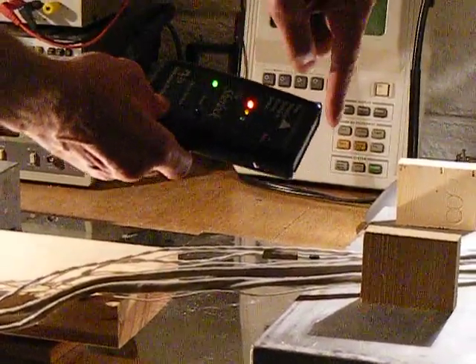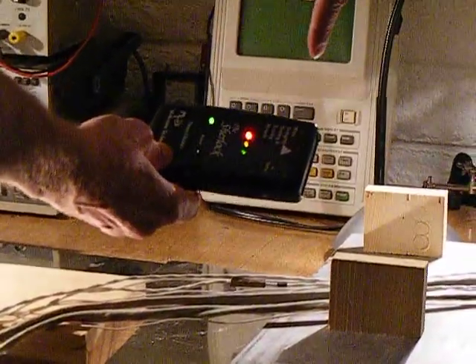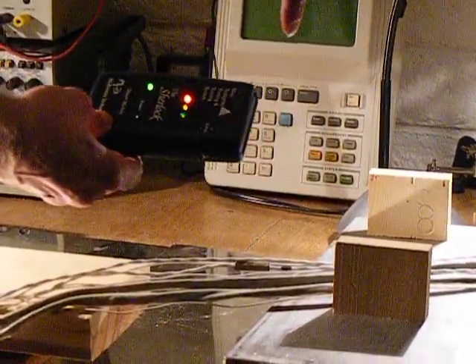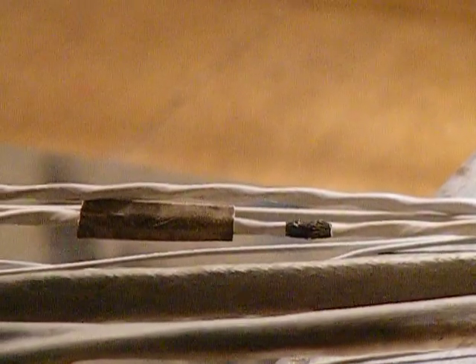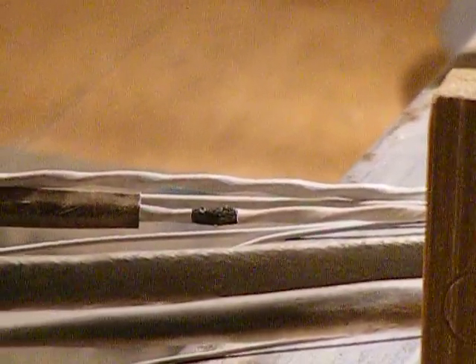And if we were to take this arrow, right where it starts to diminish, right there, follow that arrow straight down, and there will be our short. And there is our short, where the mesh shielding is contacting the core wire, causing it to short out.